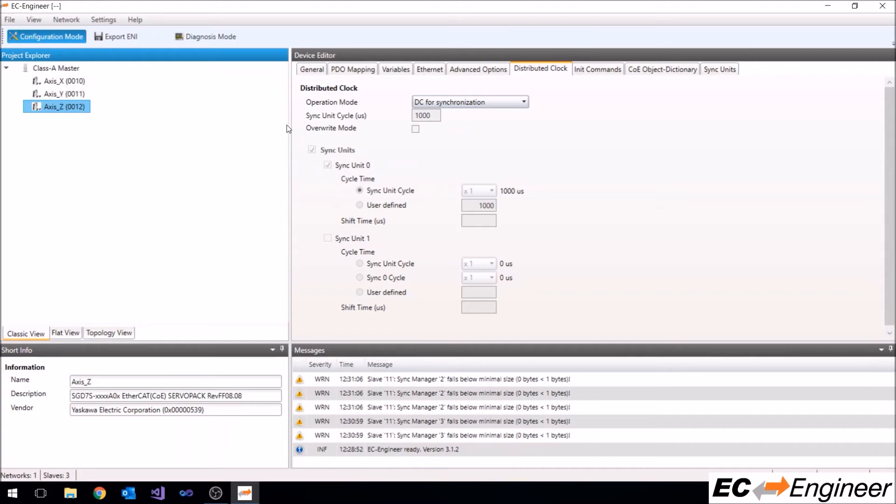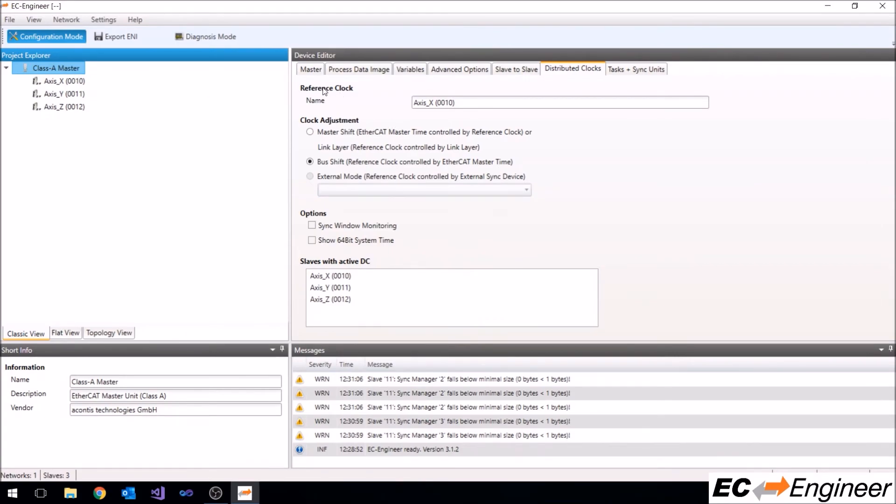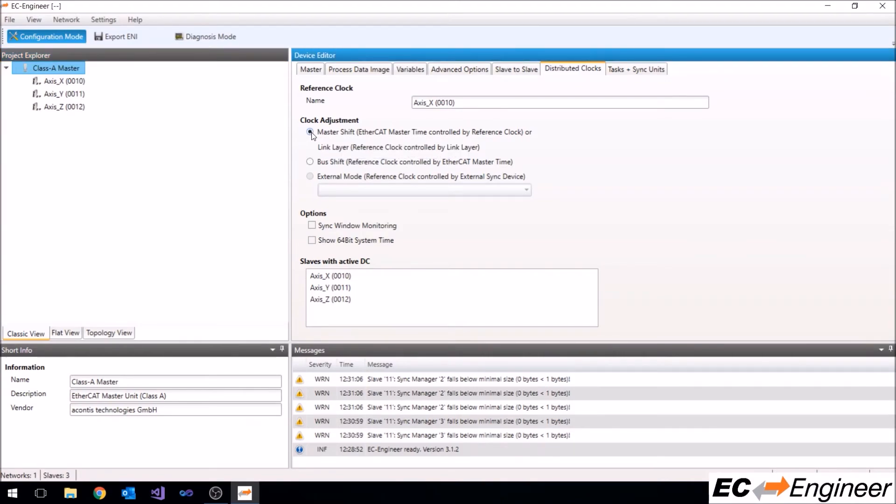You can also change how the master will synchronize with the slave devices. Click on the master in project explorer and under the distributed clocks tab you can see which slave is the reference clock and then adjust how the master will be synchronized with the reference clock.